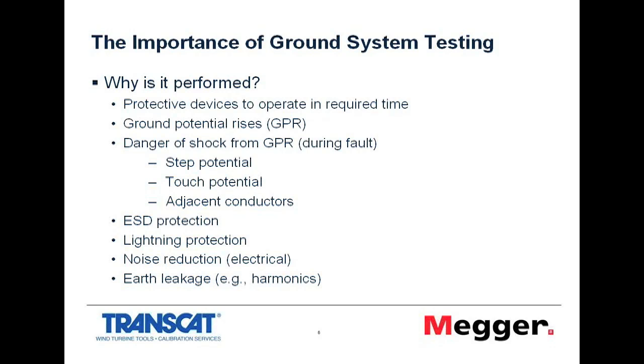In addition to that, the protection provided against electrostatic discharge is often totally reliant on the quality of the ground connection, and lightning protection, which is obviously a very important area for wind turbines, is also reliant on a good connection to ground. In addition to that, the ground connection is an effective way of taking any induced noise or any earth leakage into ground, and in a way which prevents problems anywhere else on the system. So overall, there are many reasons to ensure that a good and reliable connection to ground is available over a period of time.